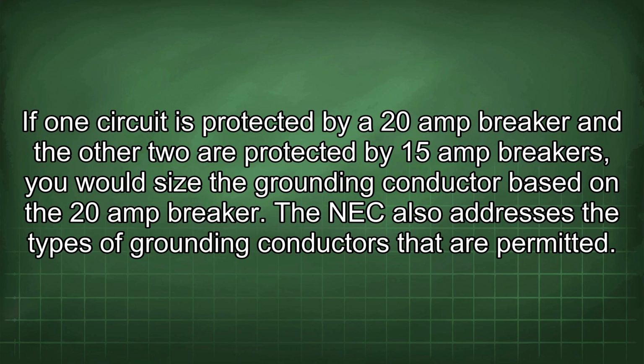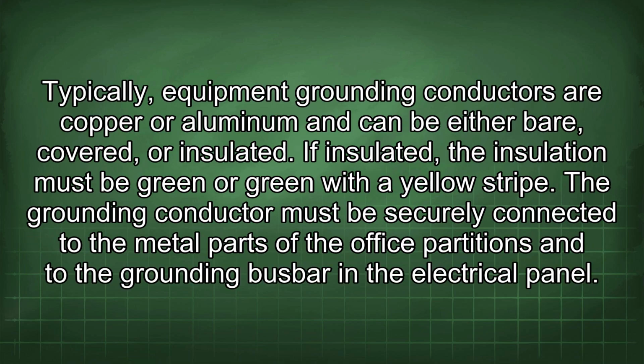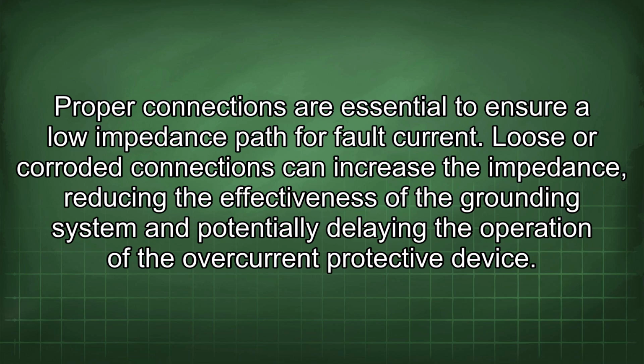The NEC also addresses the types of grounding conductors that are permitted. Typically, equipment grounding conductors are copper or aluminum and can be either bare, covered, or insulated. If insulated, the insulation must be green or green with a yellow stripe. The grounding conductor must be securely connected to the metal parts of the office partitions and the grounding busbar in the electrical panel. Proper connections are essential to ensure a low impedance path for fault current. Loose or corroded connections can increase the impedance, reducing the effectiveness of the grounding system and potentially delaying the operation of the overcurrent protective device.